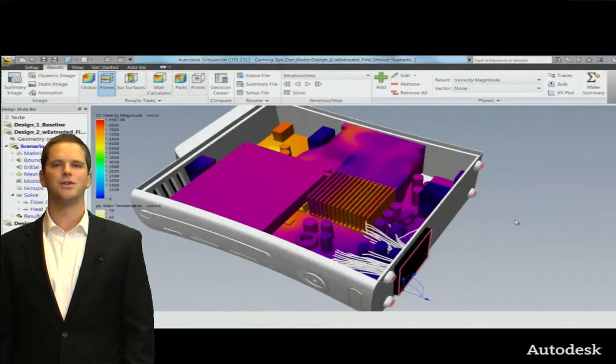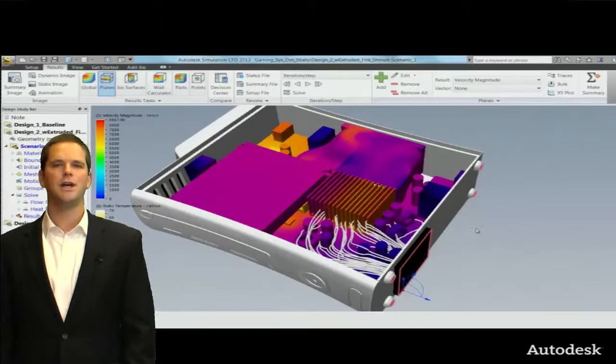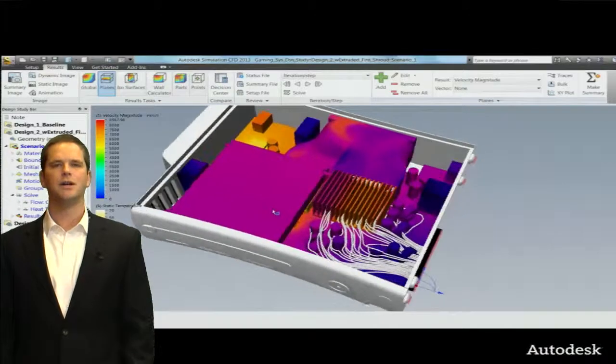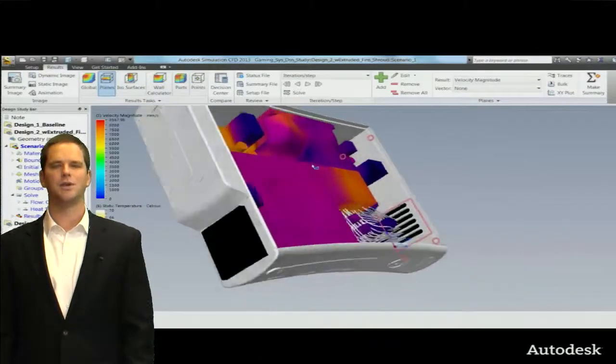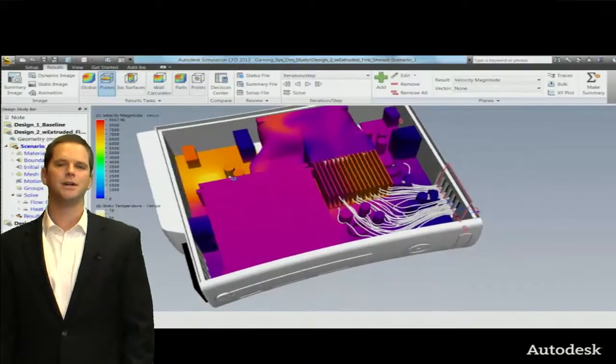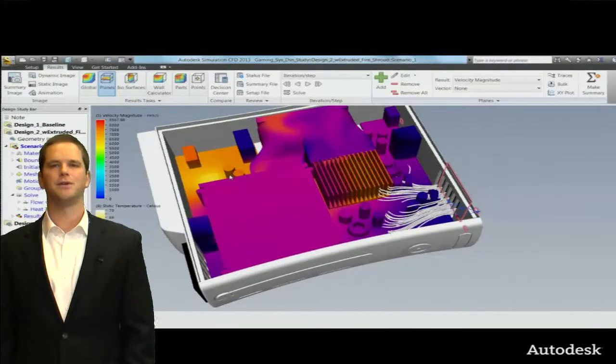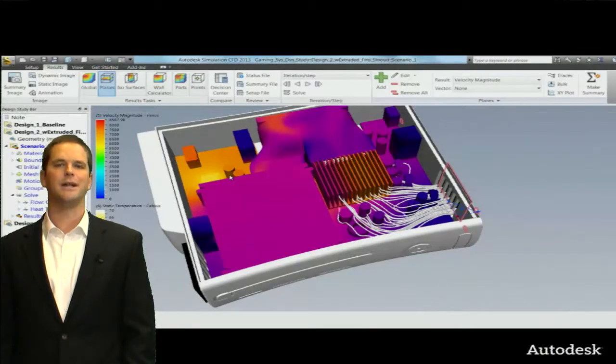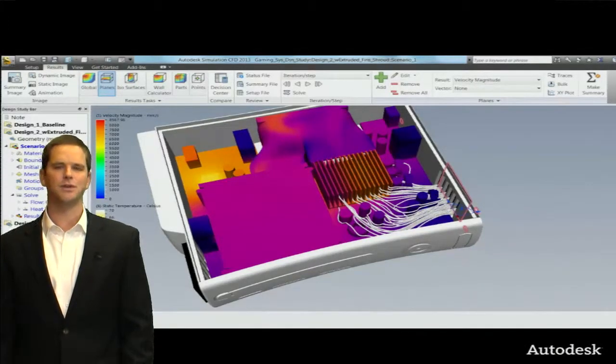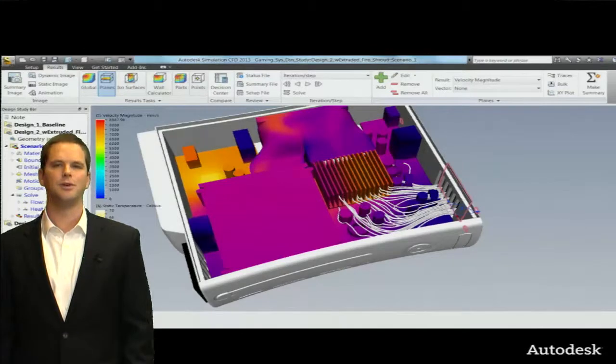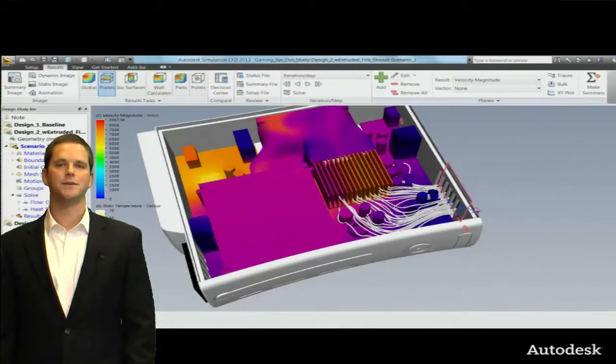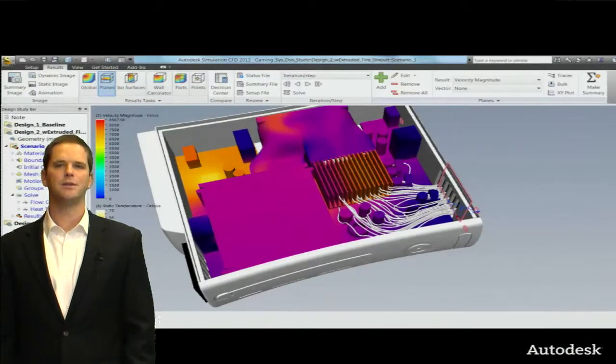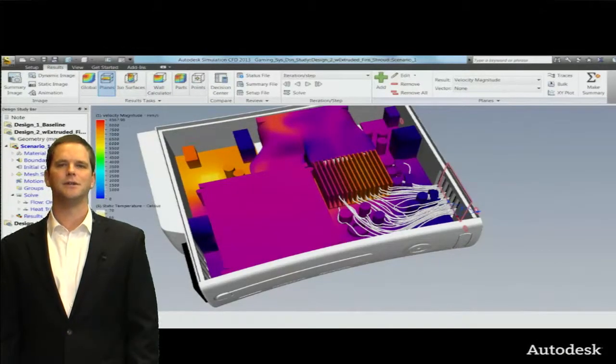The last shot here is just again using that thermal camera, animating some of the trace particles through so we can track how they migrate through the box, where they tend to go. Are there any areas of stagnation or recirculation? Those are problematic. Those are areas that would get very hot. If you've ever seen a stagnation or recirculation zone directly over a hot component, you know what that equates to and it's thermal runaway. So we want to make sure we avoid that as well and just be really strategic and intentional with how we're directing the airflow.